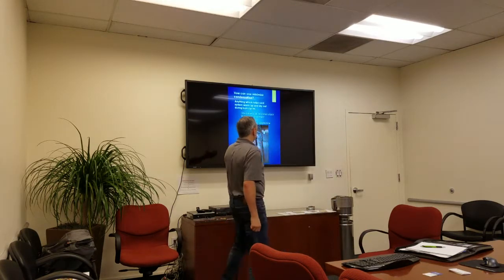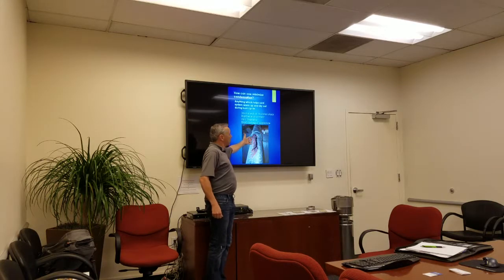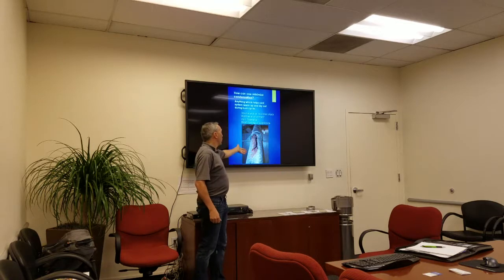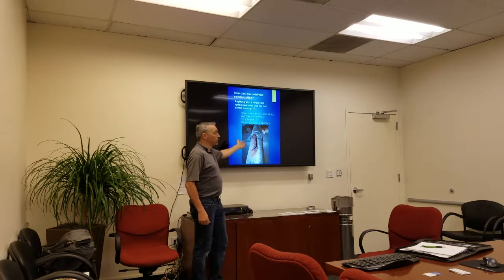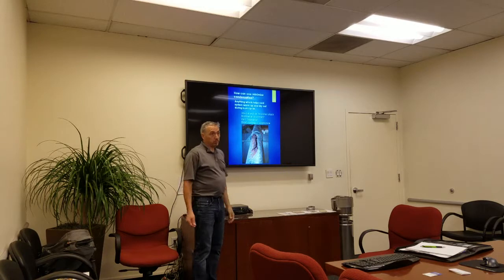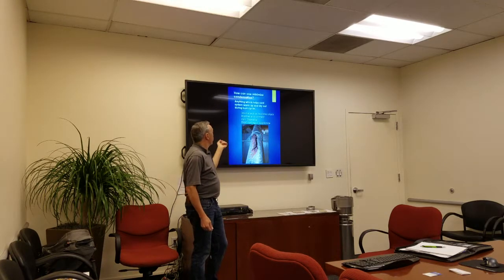This is a stack that had lots of condensation in it. It's a galvanized sheet metal stack and carbonic acid is very corrosive to it. Once you see things like this, your system is compromised and people could be seriously hurt or killed.